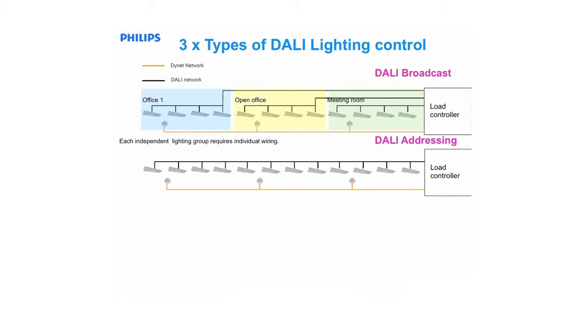During the commissioning process of the lighting control system, the individual ballast addresses must be discovered. This is what's referred to as DALI enumeration. These are the numbers in black that are appearing now. The individual addresses of the ballast are physically located and entered into the lighting control system.